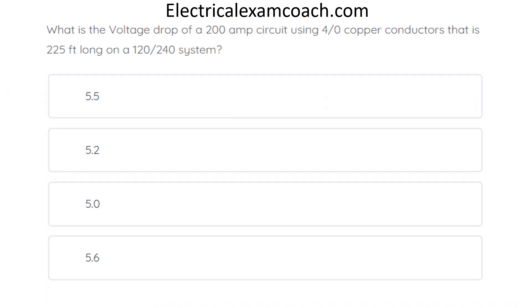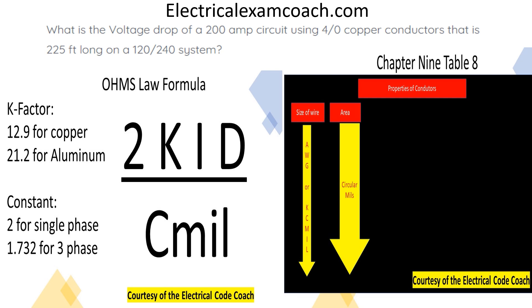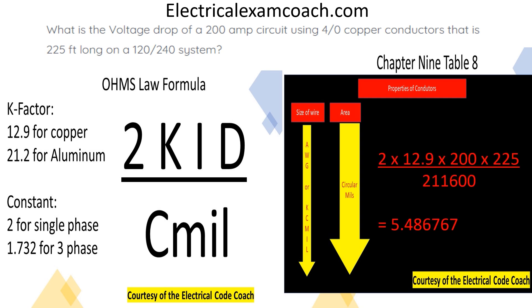What is the voltage drop of a 200-amp circuit using 4-aught copper conductors that is 225 feet long on a 120–240-volt system? The correct answer is 5.5. For this one, we use our Ohm's Law formula: 2KId over CM. The constant is 2, K-factor is 12.9 for copper, then current and distance divided by circular mils. We head to Chapter 9, Table 8 to get the circular mil value for 4/0 copper. The formula gives us: 2 × 12.9 × 200 × 225 ÷ CM = 5.48676, which we round up to 5.5.